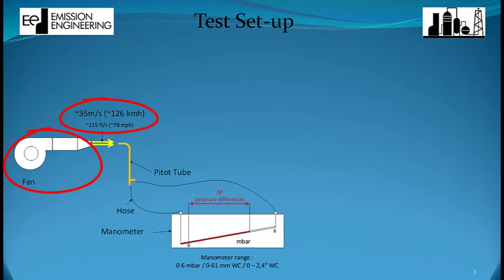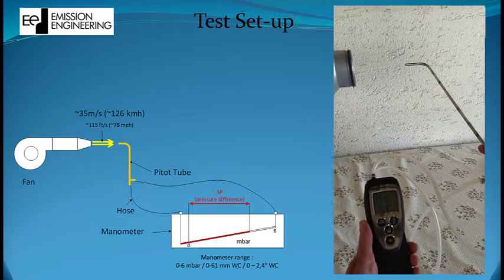In order to verify the velocity, we use the pitot tube, measuring the pressure drop and back calculating the velocity from there. As soon as the fan is started, the pitot tube quickly measures the air velocity.